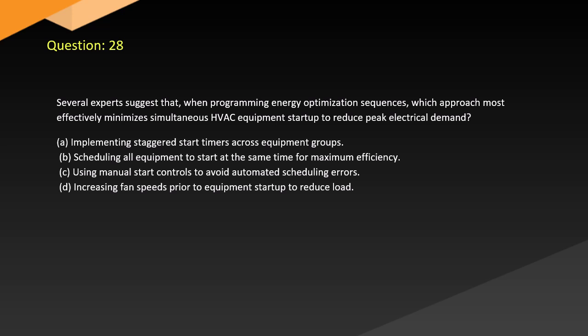Question 28. Several experts suggest that when programming energy optimization sequences, which approach most effectively minimizes simultaneous HVAC equipment startup to reduce peak electrical demand? A. Implementing staggered start timers across equipment groups. B. Scheduling all equipment to start at the same time for maximum efficiency. C. Using manual start controls to avoid automated scheduling errors. D. Increasing fan speeds prior to equipment startup to reduce load.